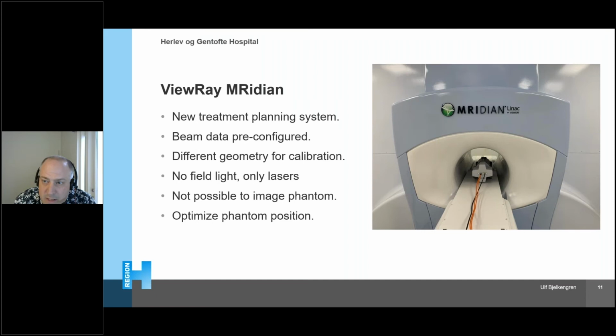It's not only a completely new Linac, it's a completely new treatment planning system. It's a new type of Linac, MR Linac. So you have the magnetic field, you don't have the field light, you don't have any imagers and so on. So you have to think a little bit different. You also have a pre-configured beam data. You have a different geometry for calibration. So you can't reach SSD 100 in this machine.